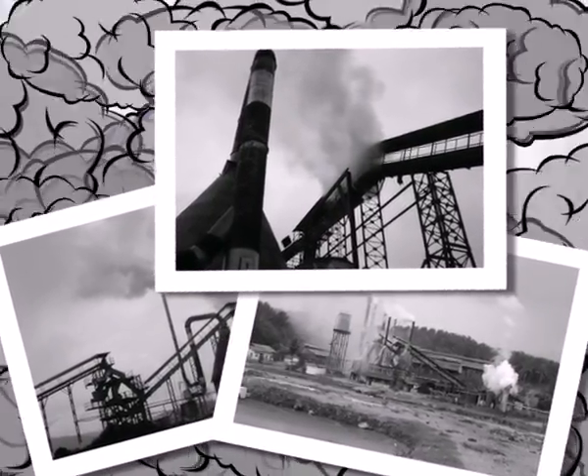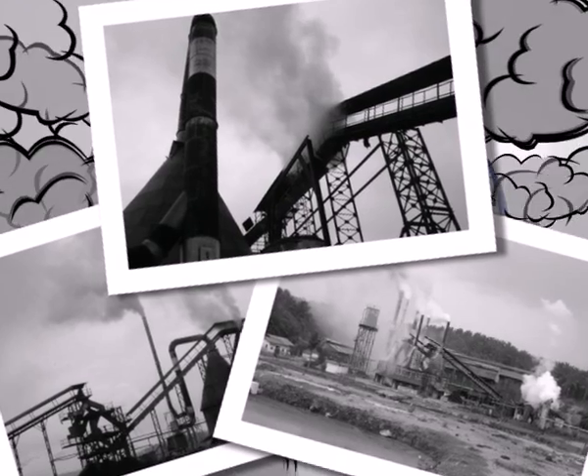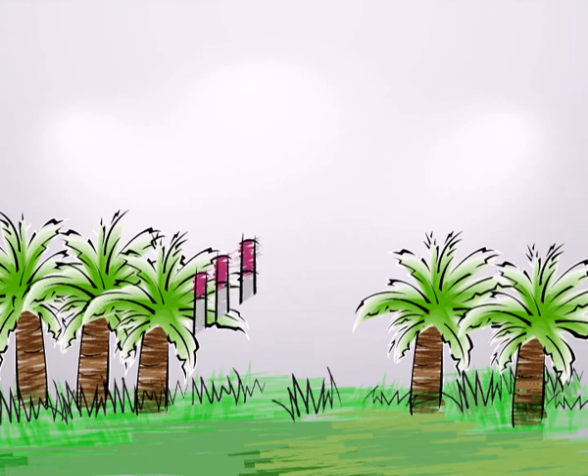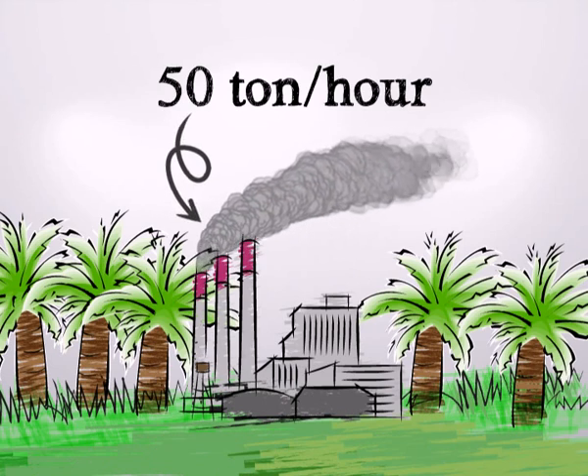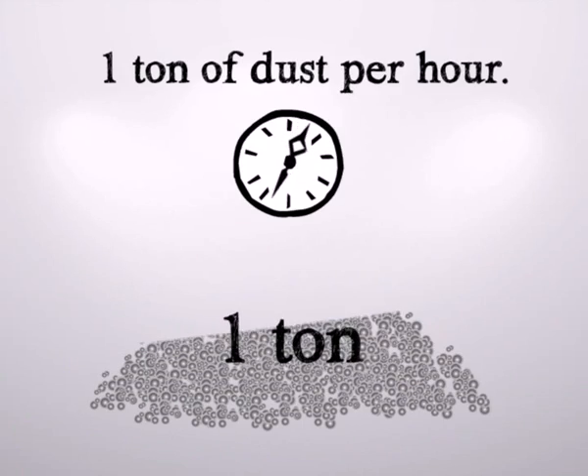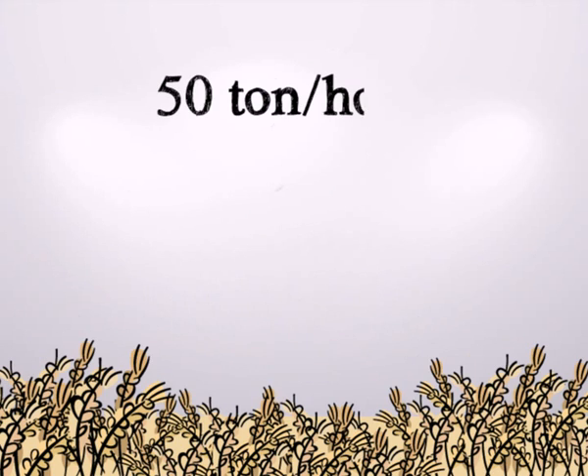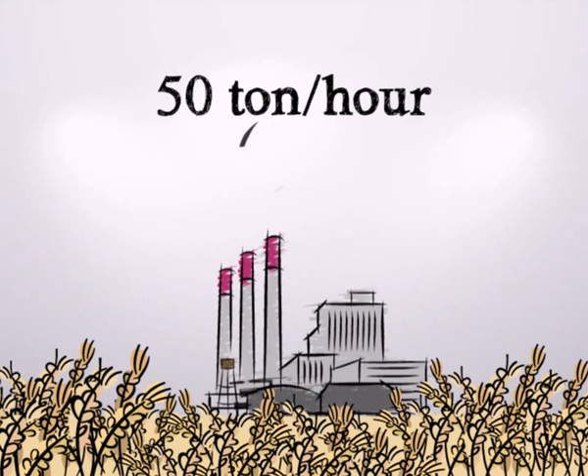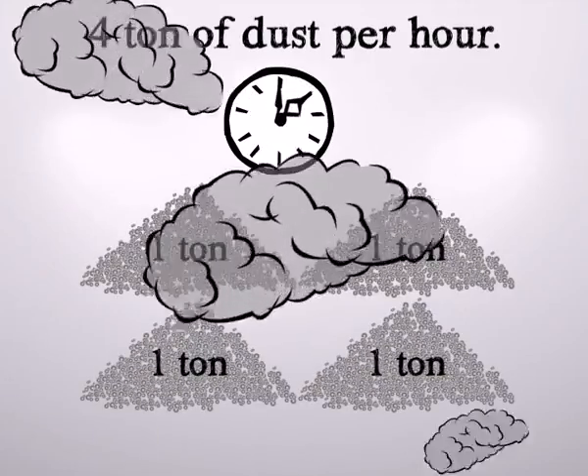Reducing the dust, however, needs an efficient dust collector. A typical 50 ton per hour palm oil fiber shell fired boiler will generate one ton of dust per hour. A 50 ton per hour rice husk fired boiler will generate four tons of dust every hour.